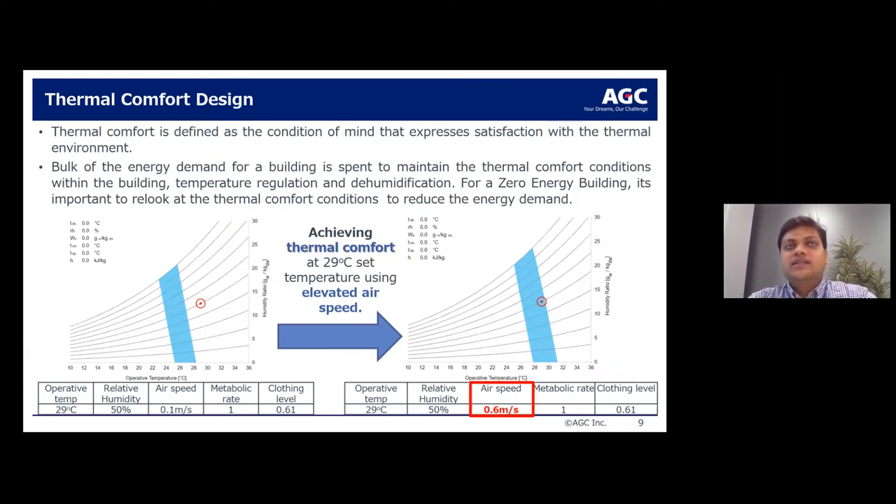Another important aspect is to re-look at thermal comfort design. Most of the time we design according to set points of around 24°C. Looking at two psychrometric charts from the CBE thermal comfort tool: a high operative temperature of 29°C is far beyond the thermal comfort zone. But for the same operative temperature of 29°C, if you increase the air speed (ASP), those same conditions fall within the thermal comfort zone. Thermal comfort holds a very impactful opportunity to reduce energy use.